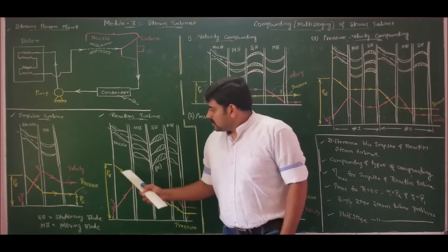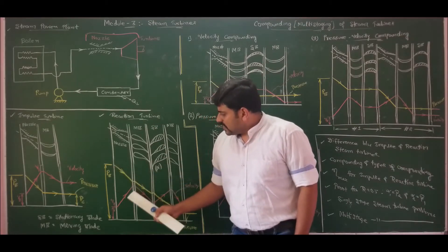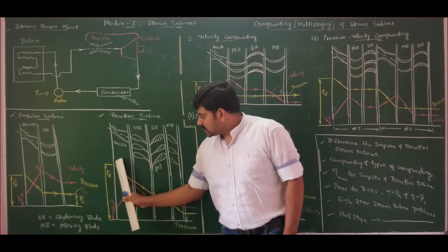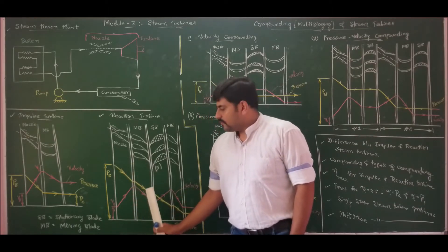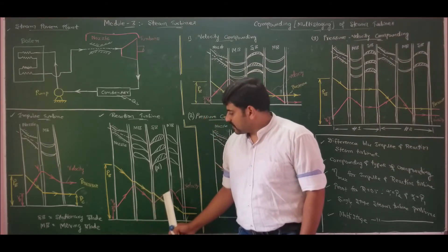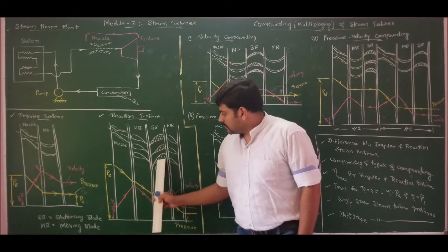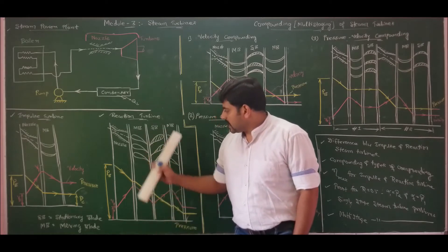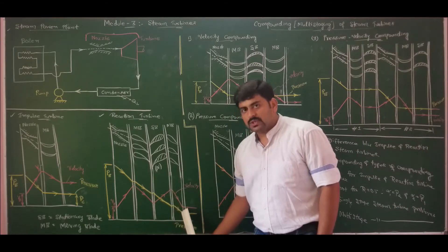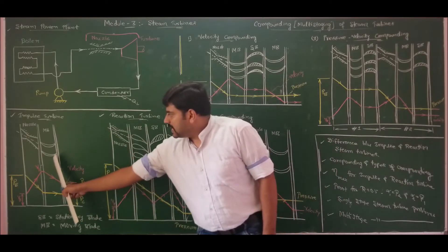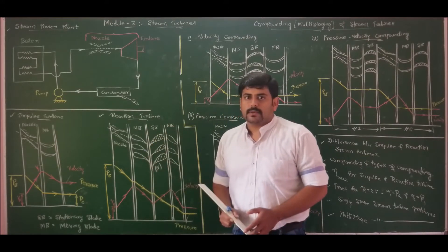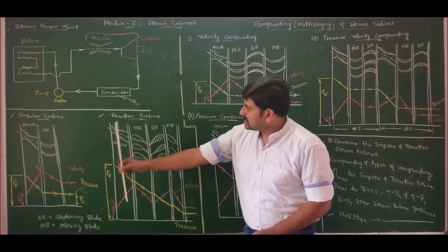In the case of reaction turbine, plotting variation of velocity and pressure over the steam passage length, we observe steam expands partially in the nozzle and remaining expansion takes place in the moving blade. Velocity increases in the nozzle and decreases in the moving blade. In the next stage, the stationary blades act as nozzles — velocity increases and pressure decreases. In the moving blades, both velocity and pressure decrease. The blades are symmetrical in case of impulse turbine, whereas blades are airfoil-shaped in case of reaction turbine.